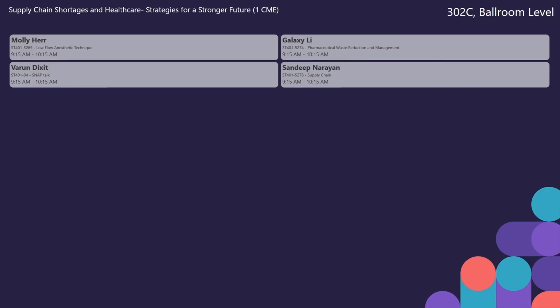We have GE machines that are placed. It's a similar situation where the soft keys that are programmed into the ventilators are all higher flow rates. So we work with GE and we reduce the default keys and the soft keys. So when you hit the default keys, it goes to a liter as the default setting. I think that makes it easier for providers to accept low flows. It is one less step for them to cut the flows from 2 to 1 liters manually. It helps change behaviors and makes it easier for providers in day-to-day practice. I don't know about Draeger's, but I think you should be able to do it if you reach out to Draeger.